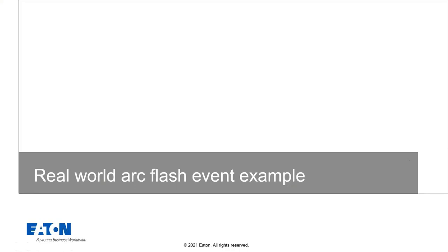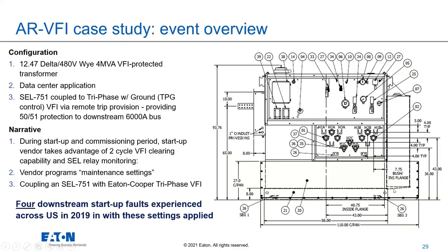So now we'll move on to our real world arc flash event. This is a little bit more exciting for us who don't get to see that often. So we've now got a fully integrated piece of equipment. This is just an example of a VFI transformer, so again, an integral vacuum interrupter inside of the transformer. But the big piece here is that, in addition to that secondary set of CTs, we're also having that onboard relay. We also have the local relay. In this case, it was an SEL-751 to pick up that secondary overcurrent and trip the VFI.